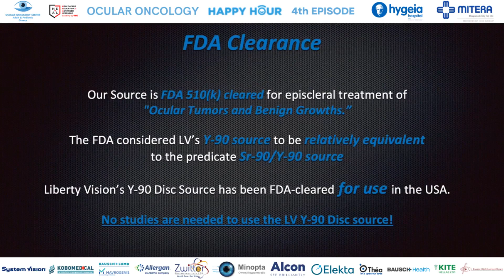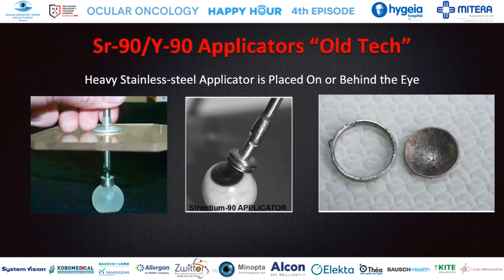On your left, see the prior strontium-90 yttrium-90 device, which was commonly and widely used for ocular tumors and benign growths in the United States. This old predicate handheld device was used for anterior application and was opaque, metallic, and therefore heavy and relatively inflexible. Though never commercially available, the custom European strontium-90 yttrium-90 radiation disc on your right and its carrier ring allowed the surgeon to sew it to the sclera, primarily beneath ocular tumors. Though the FDA considered our yttrium-90 radiation source to be equivalent to the device on your left, both devices and methods needed improvement.